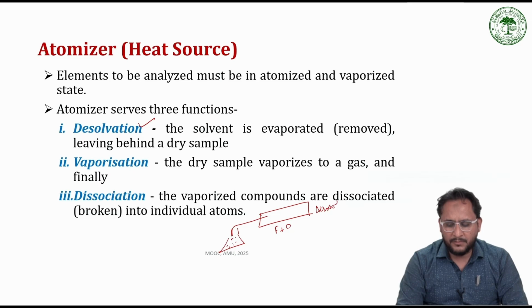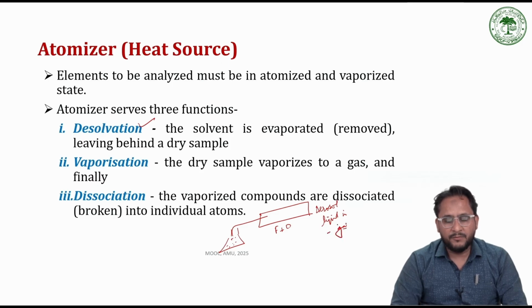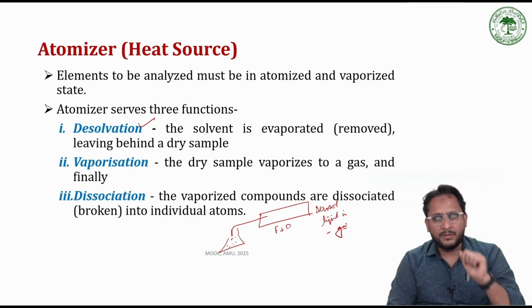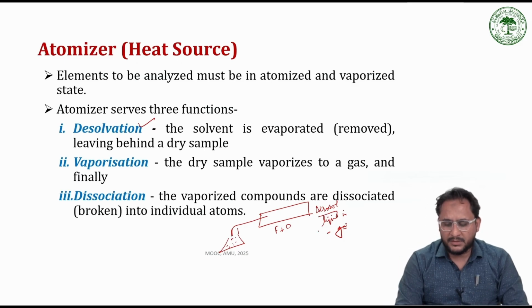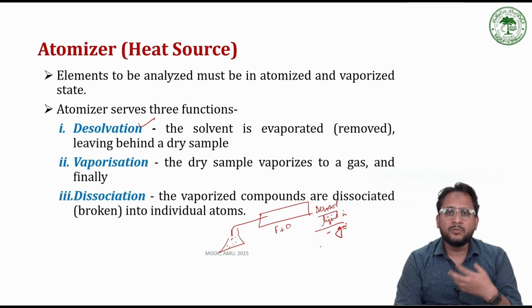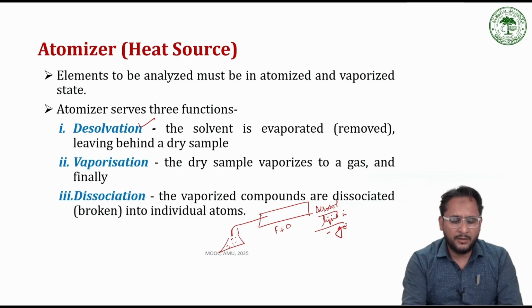Now this means that we have an aerosol which contains liquid sample in a gas. So we still have the sample present in solvent molecules in the form of droplets distributed in this aerosol.